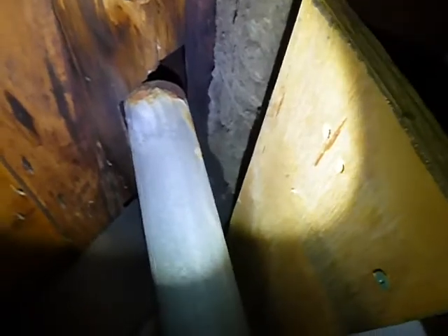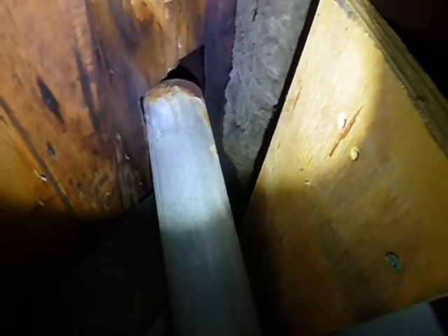This is the flue — see all that discoloration up there? That's the flue for the water heater and it doesn't go through the ceiling to that vent cap up on the roof. So that's just wrong — that's carbon monoxide coming back into the house, that's heat, that's a fire hazard. That's wrong on several different levels.